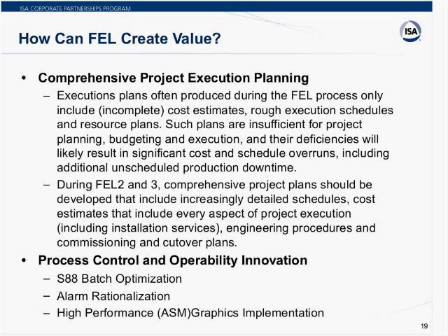And then finally, and Charlie's going to touch on these a little bit more in a minute, so I won't go into any detail, but some of the same things Nick talked about. S88 batch optimization. There's a lot of batch systems out there running on older DCSs and PLC platforms that were not implemented using S88. They're perhaps 30 years old. There's an opportunity to bring those processes up to modern standards and thereby increase efficiency, interoperability, safety, all those kinds of things by using those modern standards. Alarm rationalization, high performance graphics, using ASM standards, cybersecurity. So use the FEL process to look at those kinds of opportunities and see to what degree they can be implemented and then benefit you in the long term.